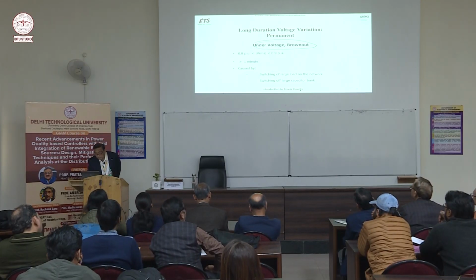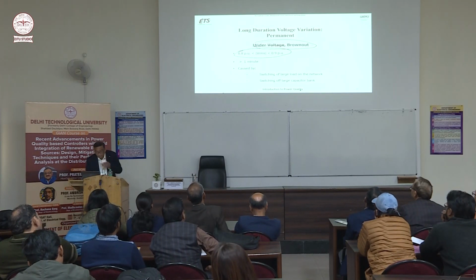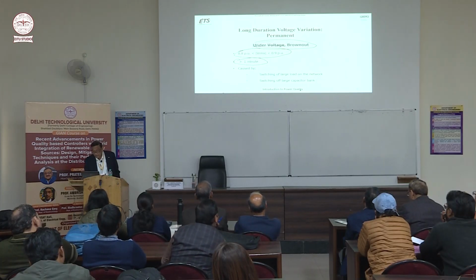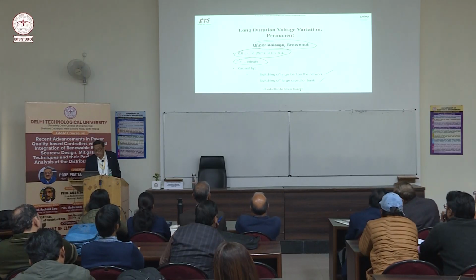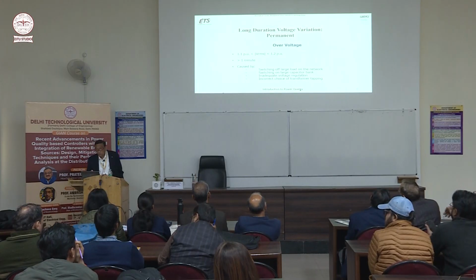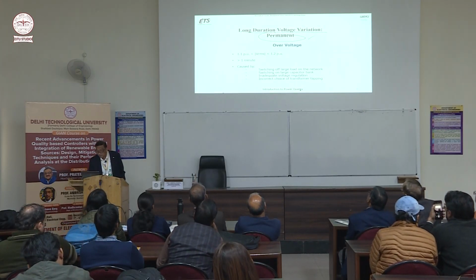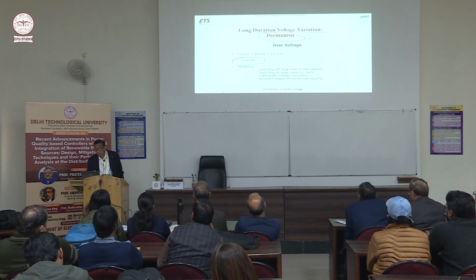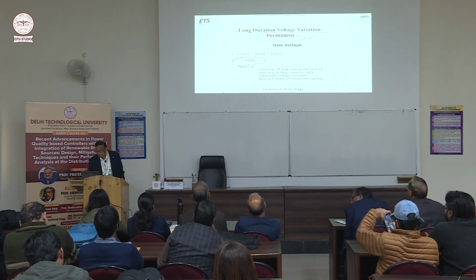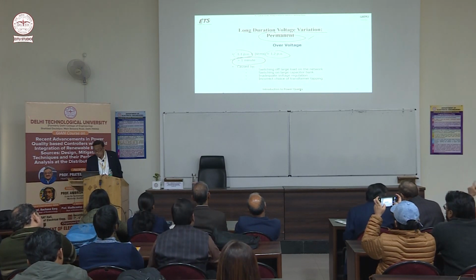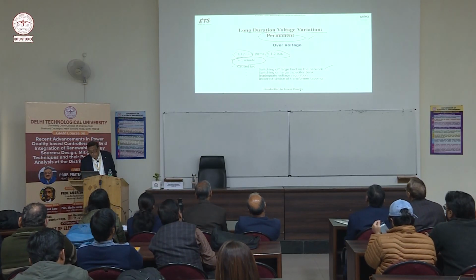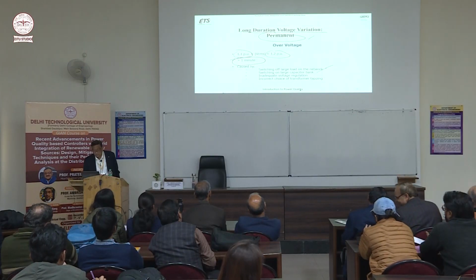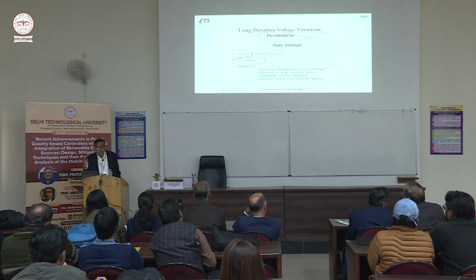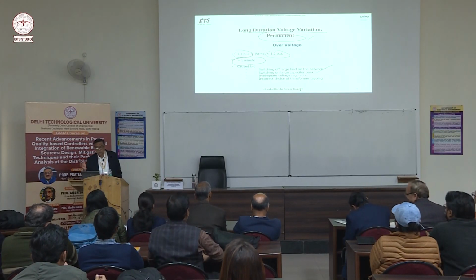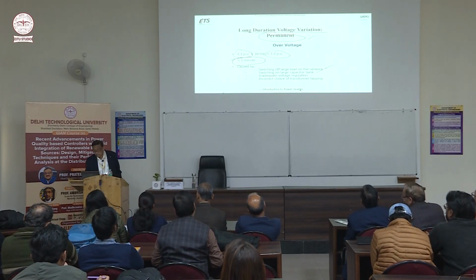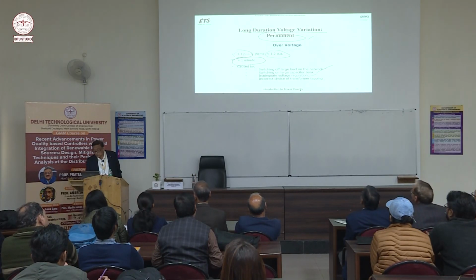So under voltage is 0.8 pu to 0.9 pu for more than 1 minute, caused by switching of a large load on the network or switching of a large capacitor bank. Over voltage, a permanent, long-duration voltage variation: if it is more than 1 minute, then we call it a long-duration voltage variation. 1.1 pu to 1.2 pu, caused by switching off a large load on the network, or switching on a large capacitor bank. Because when you switch on the large capacitor bank, it supplies the reactive capacitive current, so less current is coming from the source, so less voltage drop, and because of that there is an over voltage for a certain time. Other causes are inadequate voltage regulation and incorrect choice of transformer tappings.